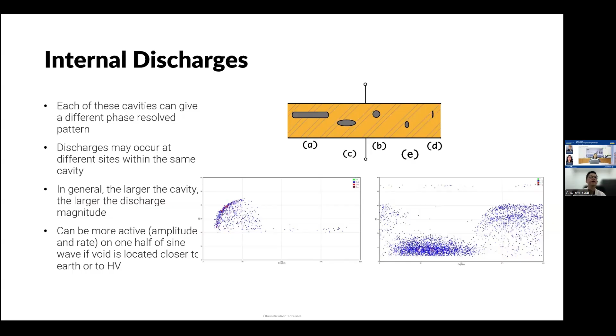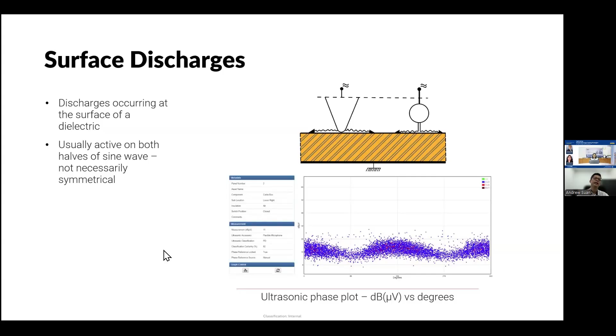Surface discharge is something more interesting - it actually looks like a hump. Sometimes we say it looks like a camel hump. When there's a surface discharge and your sensors pick it up and plot it in PRPD plots like what you see here, a lot of the time you see two humps 180 degrees apart. That more or less tells you this is actually real ultrasonic sound coming from a surface discharge. So that is roughly the shape and how it looks like.